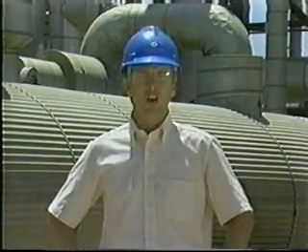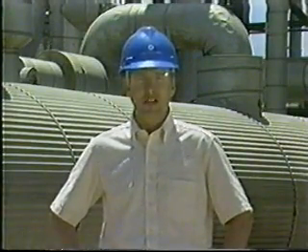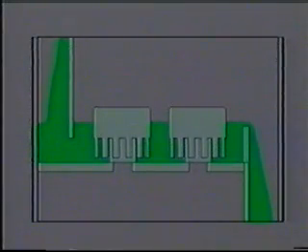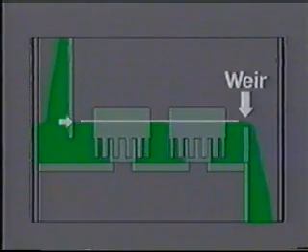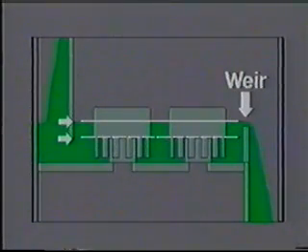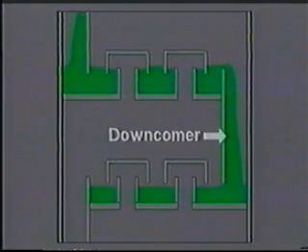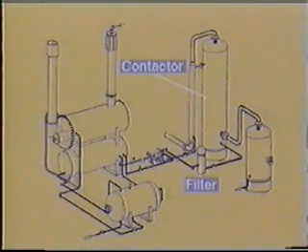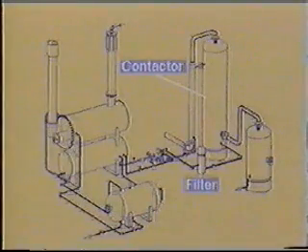Glycol is an expensive chemical, so it must be processed so that it may be used over again. Inside the contactor, a level of glycol is maintained in the trays by means of a dam called a weir. This level is above the slots in the bubble caps, so the gas is forced to bubble from under the caps up through the glycol. As the glycol level builds, it flows over the weir through a slot known as a downcomer and into the tray below. The downcomer seals the glycol passage to prevent gas from bypassing the bubble caps. As the glycol spills downward through each succeeding tray, it becomes wetter with the water absorbed from the gas, collecting at the bottom of the contactor saturated with water. This wet glycol flows out of the contactor and through a filter where solid particles and tarry hydrocarbons are removed before it enters a pump.